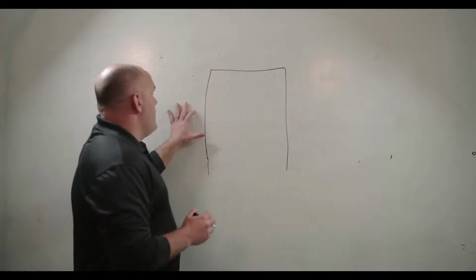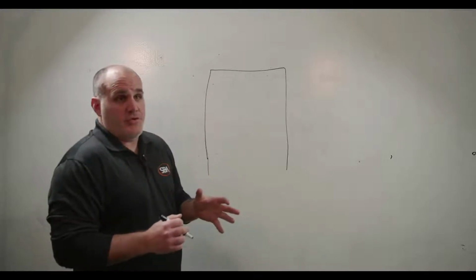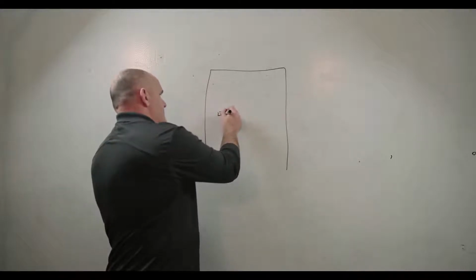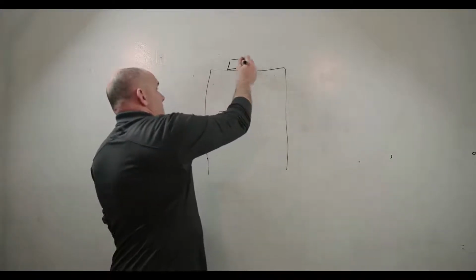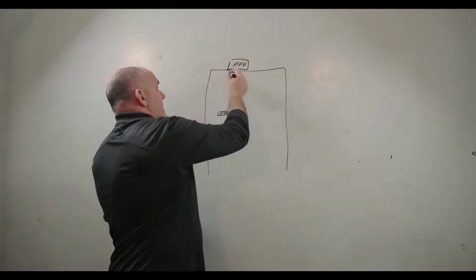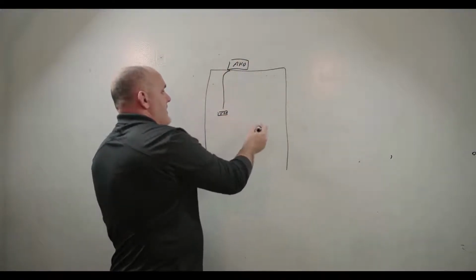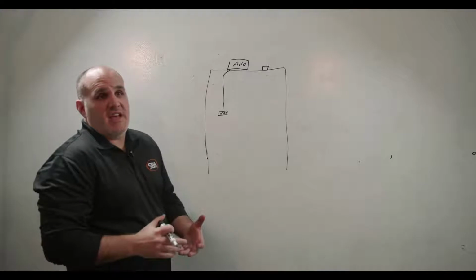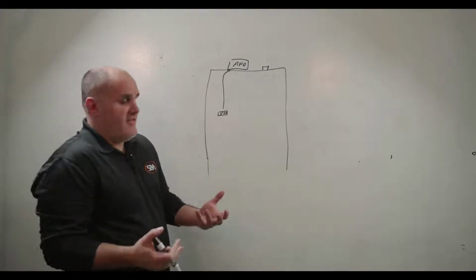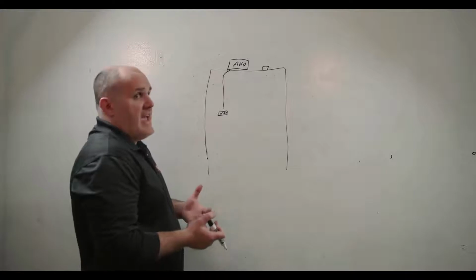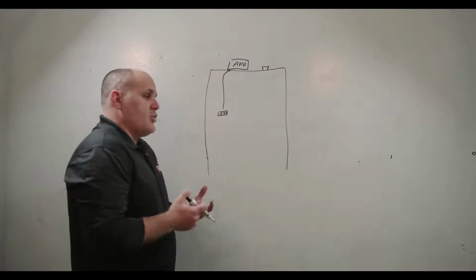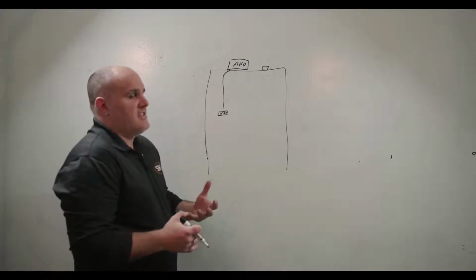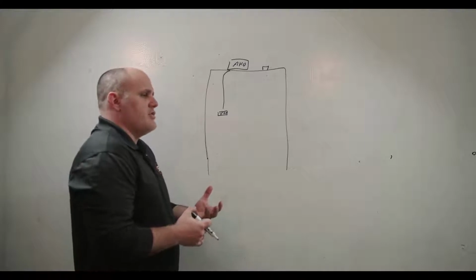So as I was saying, with airflow and pressurization, right? We've got a unit, let's say a VAV box, inside a space. And we've got an air handler on the roof of the building. And that air handler is supplying air into the VAV, and then we maybe have exhaust. And I want to make sure that we understand there is exhaust and then there's relief, right? So exhaust is taking bad stuff out of the space. Relief is relieving pressure.